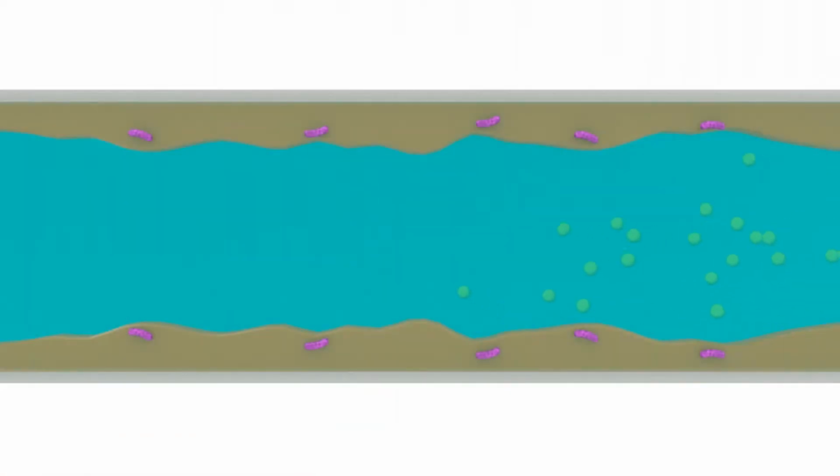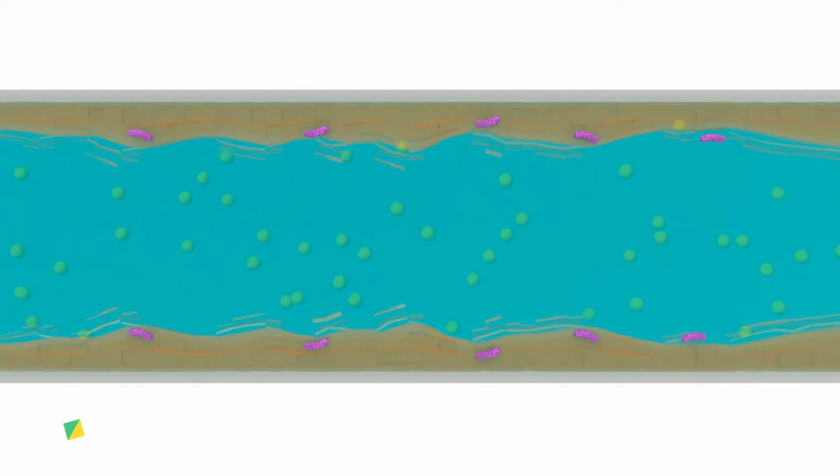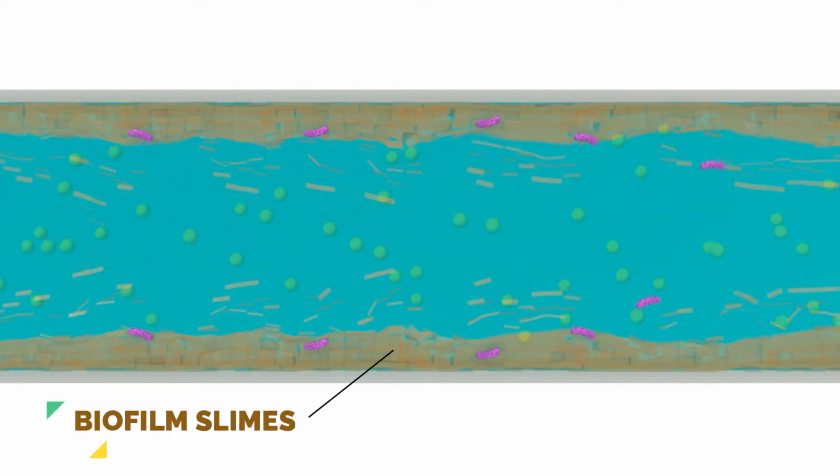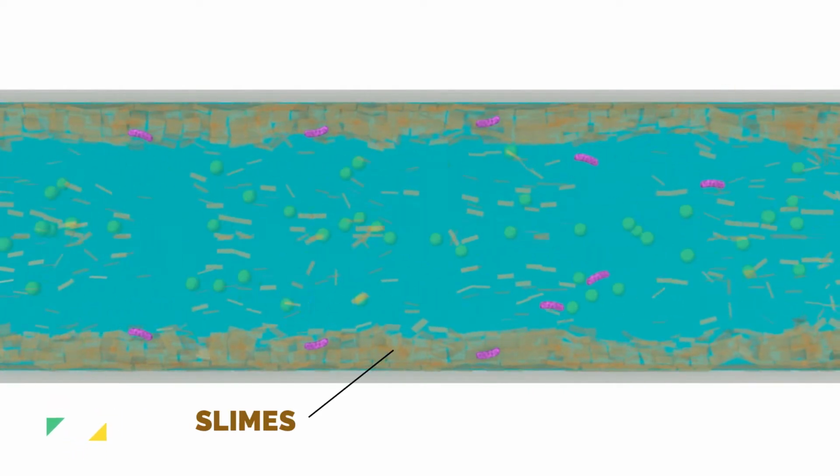These gaseous properties also make chlorine dioxide highly effective at clearing biofilm slimes, which protect bacteria, allowing it to multiply. As a dissolved gas, chlorine dioxide easily permeates the structure of biofilms, inactivating the component cells and causing biofilm to break up and detach from pipework surfaces.